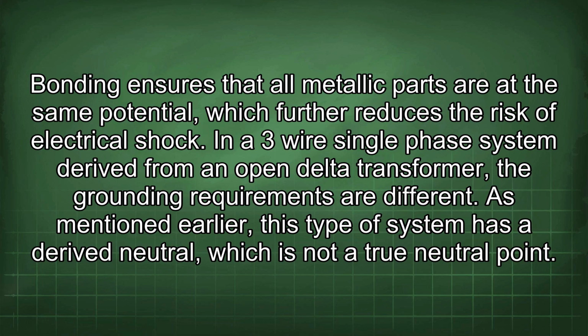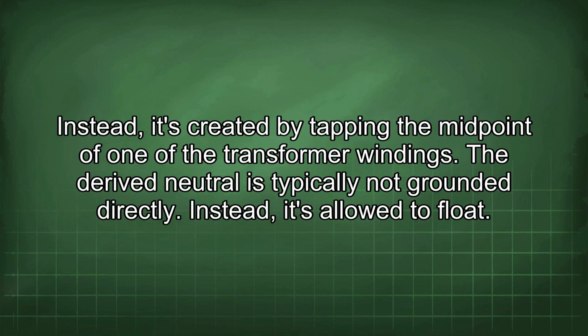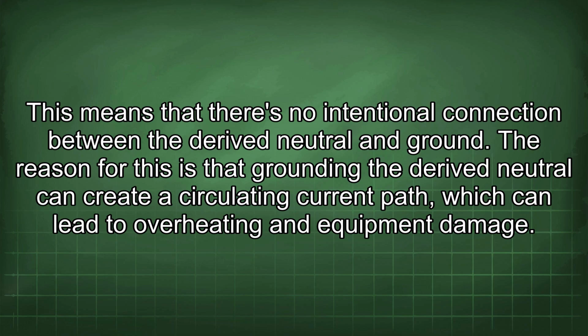In a 3-wire single-phase system derived from an open delta transformer, the grounding requirements are different. As mentioned earlier, this type of system has a derived neutral, which is not a true neutral point. Instead, it's created by tapping the midpoint of one of the transformer windings. The derived neutral is typically not grounded directly. Instead, it's allowed to float. This means that there's no intentional connection between the derived neutral and ground.